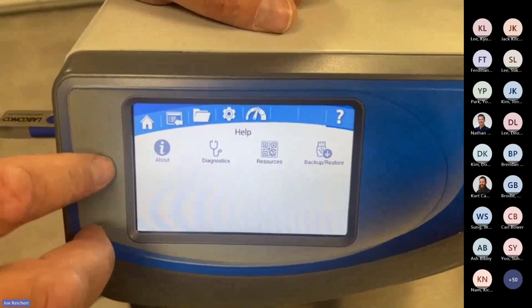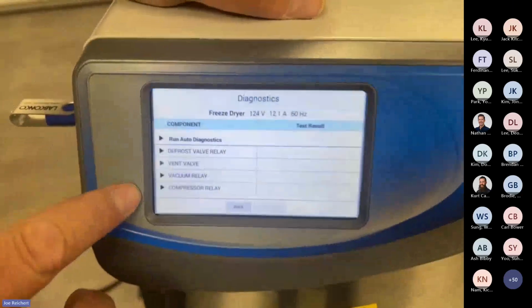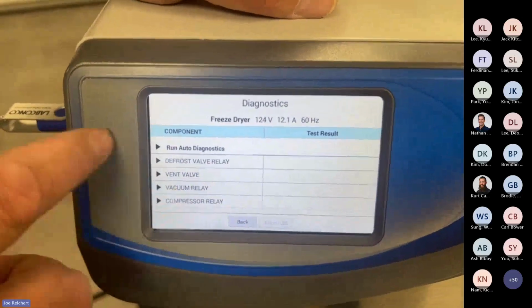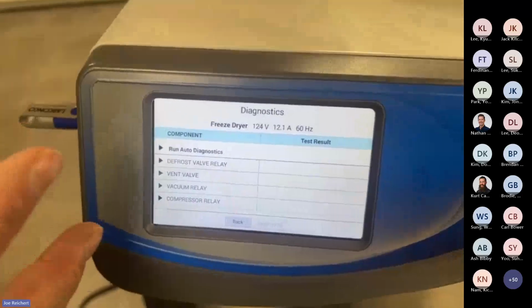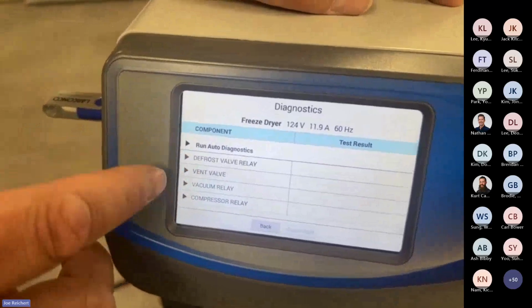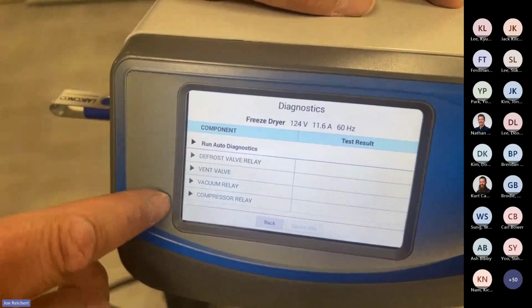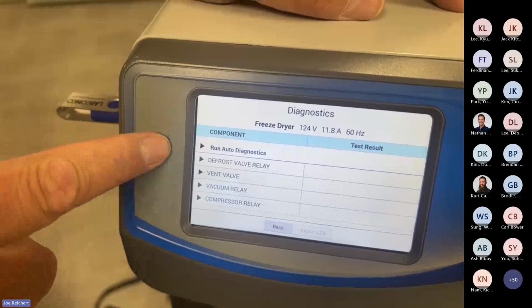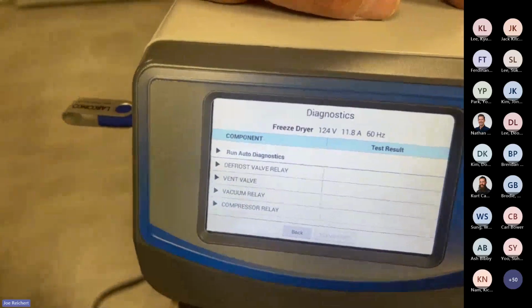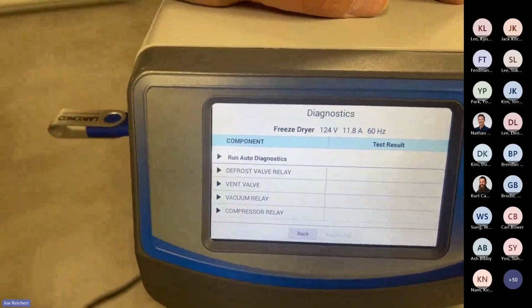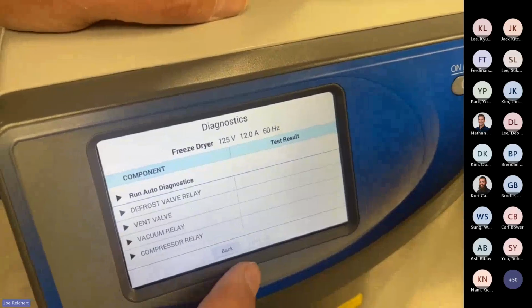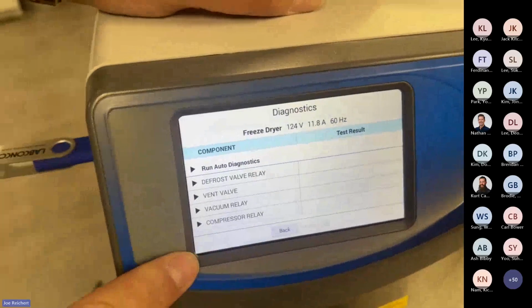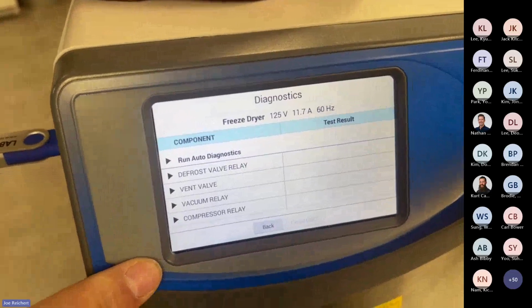On the screen, you also have your diagnostics mode where you can test a lot of different relays. This unit doesn't have any accessories to it, so there are no other options besides the 4 that you see. You can run an auto diagnostics mode. It just runs through all 4 of them step by step, where you can then export it to a USB drive if you needed to.